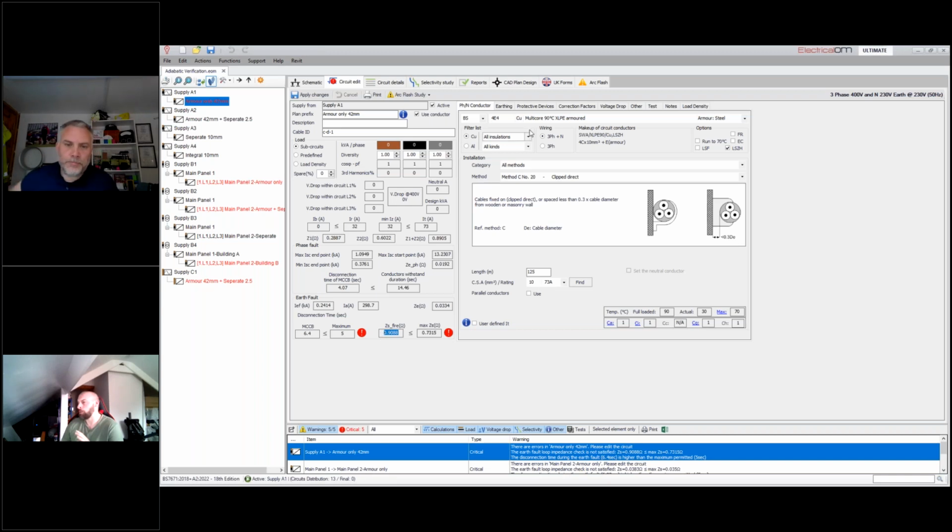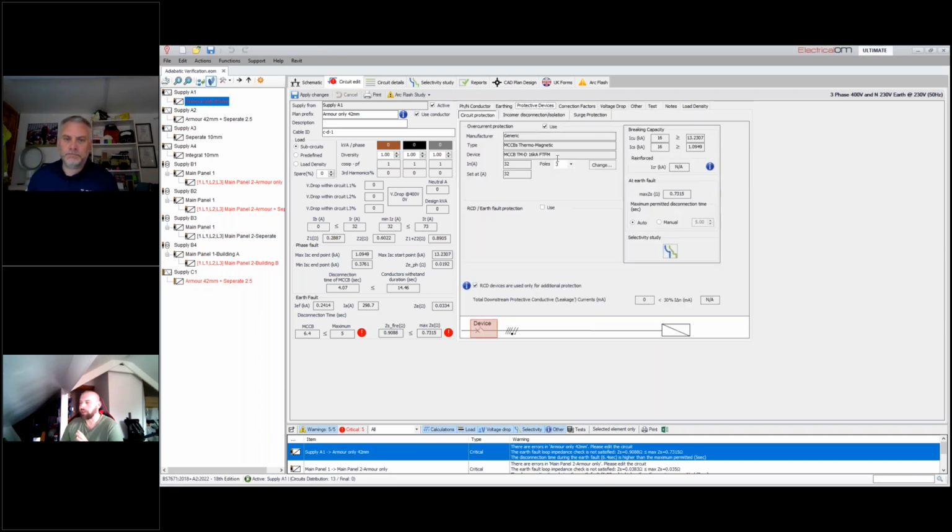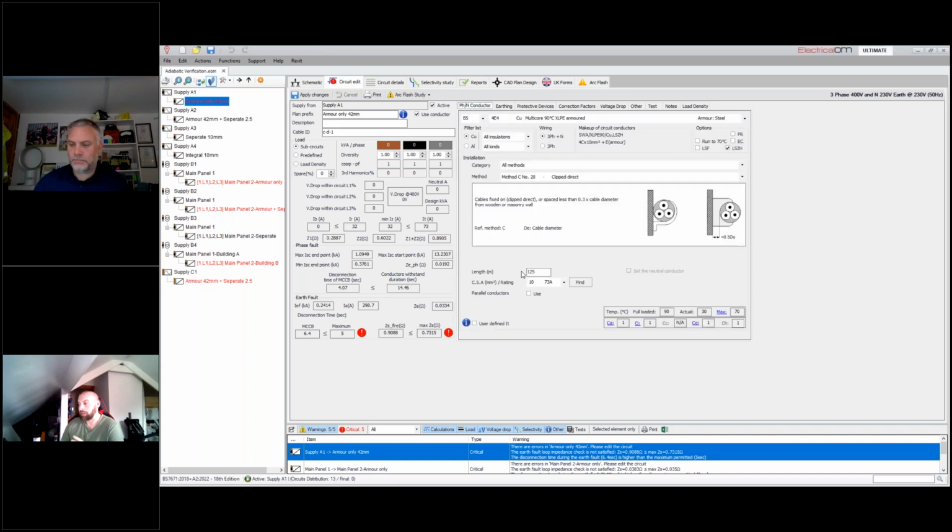So I've taken a cable, I've sized it correctly in terms of the protective device and the total load that it can take. So my cable's okay in terms of its minimum IZ for selecting the IT of our cable. But I've given it a particular length, so the only thing I'm really failing on is the overall fault loop impedance. And the first thing a lot of designers do in this situation is throw copper at it. We're going to throw in an extra earth conductor and those sorts of things. And with the smaller conductors like that, that works quite well.